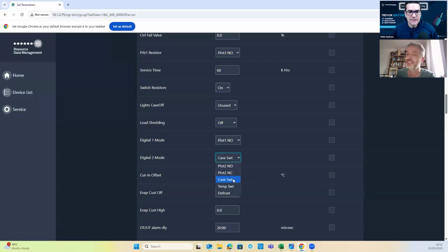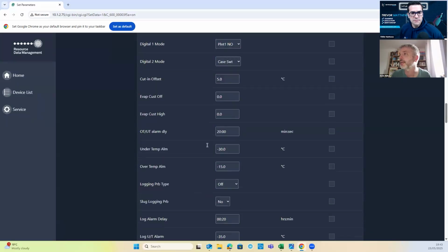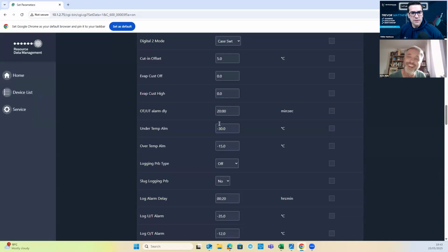Temp switch, you can switch it between temperature ranges. You can set 2 different temperatures, and that will switch between 2. Or you can tell it, if I see that input, I'm going to go into defrost. Yeah, that's quite useful for things like gas defrost. If you're initiating a gas defrost from a central controller, not something we tend to do in the UK now because gas defrost has died a death, but something that definitely still happens, I know, over there very frequently, doesn't it? So that's a good option if you want to send it a digital signal to do it. What else we got? Temperature alarms tend to be quite important. Temperature alarms, we like a temperature alarm.